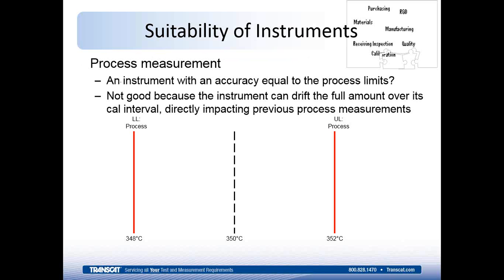Do you want to use an instrument with an accuracy that's equal to the process limits? So here we have 350 plus or minus 2 degrees, and that's what the solution has to be at. Otherwise, it doesn't treat the product correctly. You get some different results. And if you use an instrument that's the same accuracy, then you have a 1-to-1 process accuracy ratio. And that's not good because the instrument can drift the full amount during the cal interval, and that directly impacts the previous measurements you made in the process.